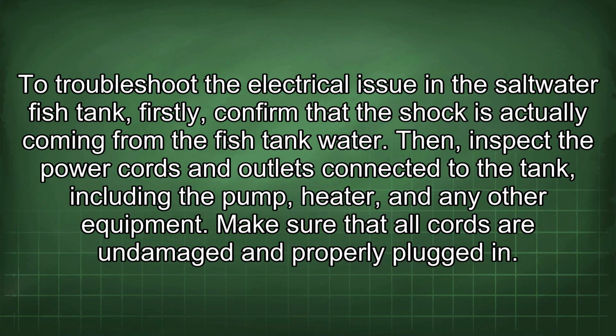To troubleshoot the electrical issue in the saltwater fish tank, firstly, confirm that the shock is actually coming from the fish tank water. Then inspect the power cords and outlets connected to the tank, including the pump, heater, and any other equipment. Make sure that all cords are undamaged and properly plugged in.